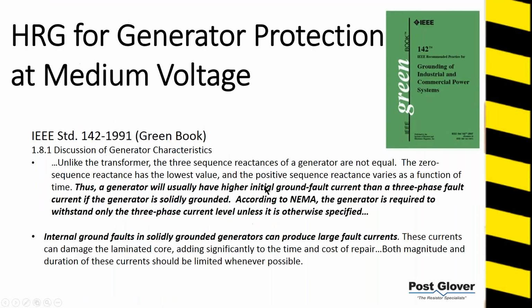So let's go to more of the why. IEEE, the Green Book, essentially, your generator has reactances, both zero sequence and positive, and there could be a disparity between the two at startup. So you could potentially have ground fault currents that are greater than your bracing. And if you have that situation, it's really bad news. So I truly recommend that you use some kind of impedance ground, which I've argued in the past. Most of the time, that means resistance grounding. That takes care of that situation with the generator.